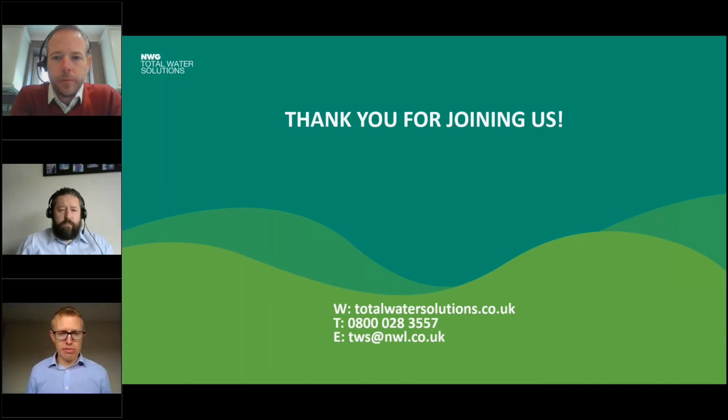So we know straight away if, for example, the sensor's broken or damaged or come out of calibration, we get an alarm. If it's offline for longer than 3 to 6 hours, we get an alarm, like a theft alarm. We could tell you if the gateway's been unplugged by the cleaners. It's never any cleaning equipment. It's always their mobile phone charger that's where it should be.